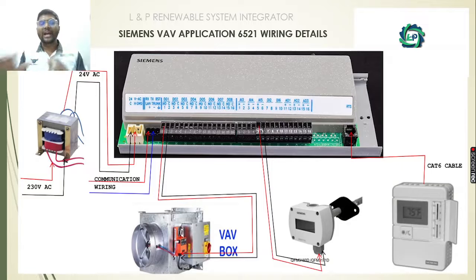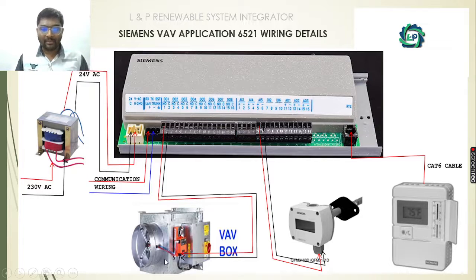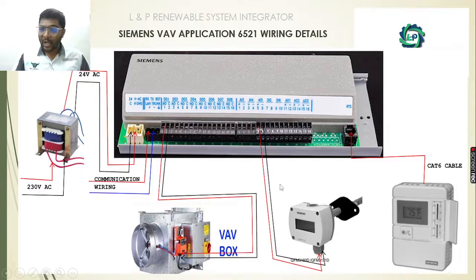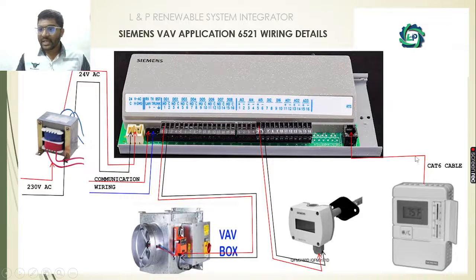This is how the electrical wiring looks inside the panel — this is how the controllers are arranged. For the controller to operate properly it needs a 24V AC supply; with a step-down transformer we convert high voltage to extra low voltage. Damper actuators connect at the DO terminals. Analog inputs are monitored from the duct sensor installed in the supply duct. The sensor output is configurable — 4–20mA or 0–10V. Room temperature readings are taken with the room temperature sensor connected to the RTS ports.